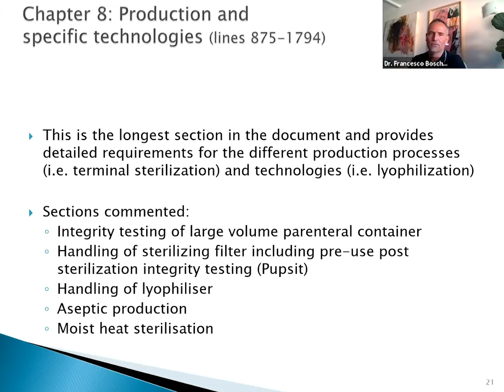And our comments were referred, for example, to point 8.41, which is a little bit ambiguous because it says that suitable BIs placed at the appropriate location should be considered as an additional method to support the validation of the sterilization process. So for us, it's not clear whether the use of BI in routine sterilization cycle is recommended. But if this is the case, we think that a validated process should not need to be confirmed every time with BIs, which is the meaning of validation.